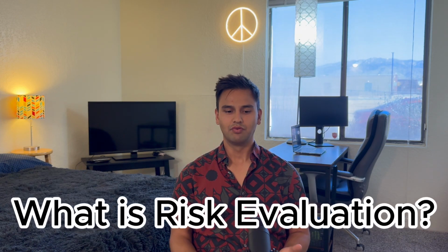So what is risk evaluation? Now you have already got all your hazards and hazardous situations from the PFMEA or DFMEA that you use in your company, and you have a list of hazards and hazardous situations, right? And you might already have a risk matrix and you know how much harm that line item can give to the patient. So now in this step we evaluate the risk. Risk evaluation involves comparing the estimated risk with pre-established criteria to determine whether they are acceptable or not, right?